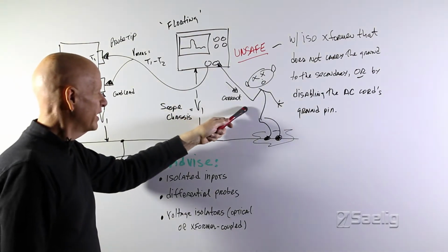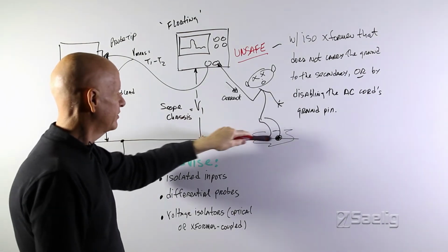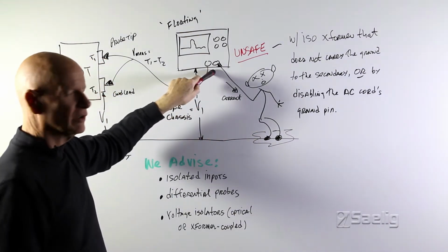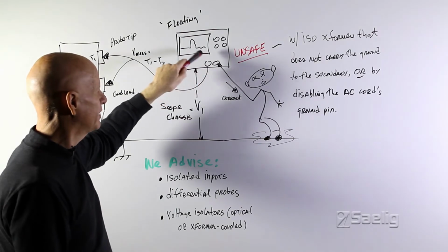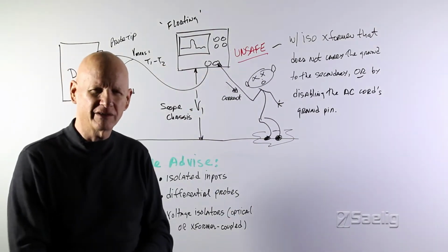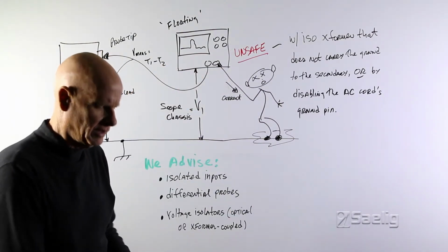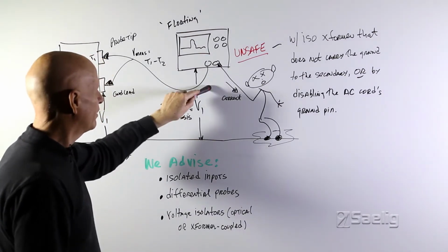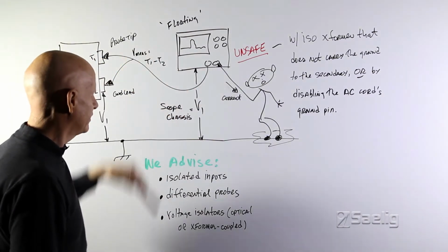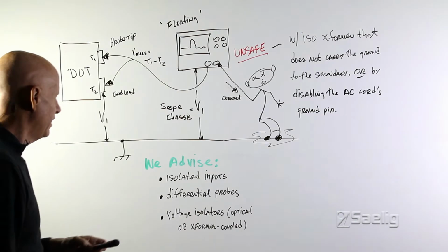And if the operator comes along and is somehow grounded or standing in water or something and touches one of these points on the scope, there's going to be a fault current that flows through him, and he's going to be uncomfortable or damaged because of that. So that's what this can result in. That's why we don't recommend it.